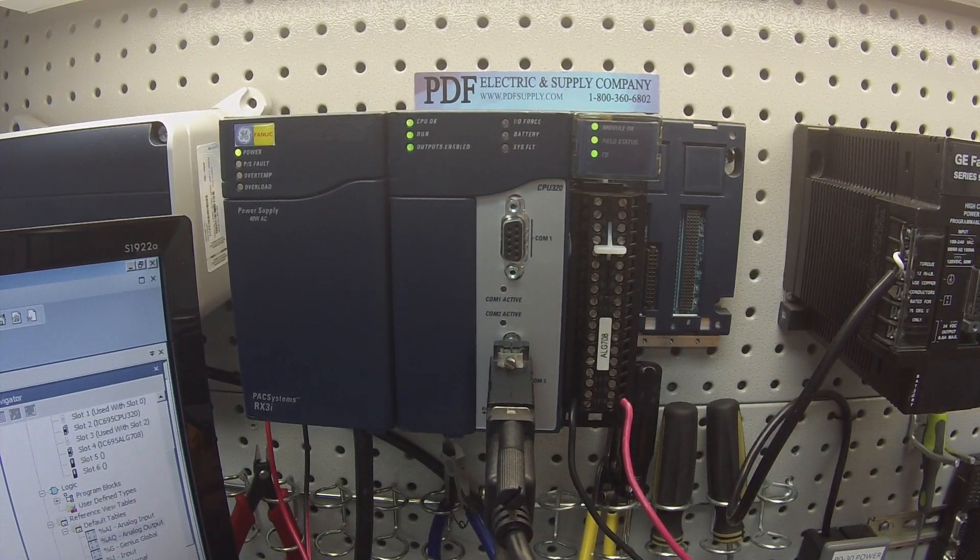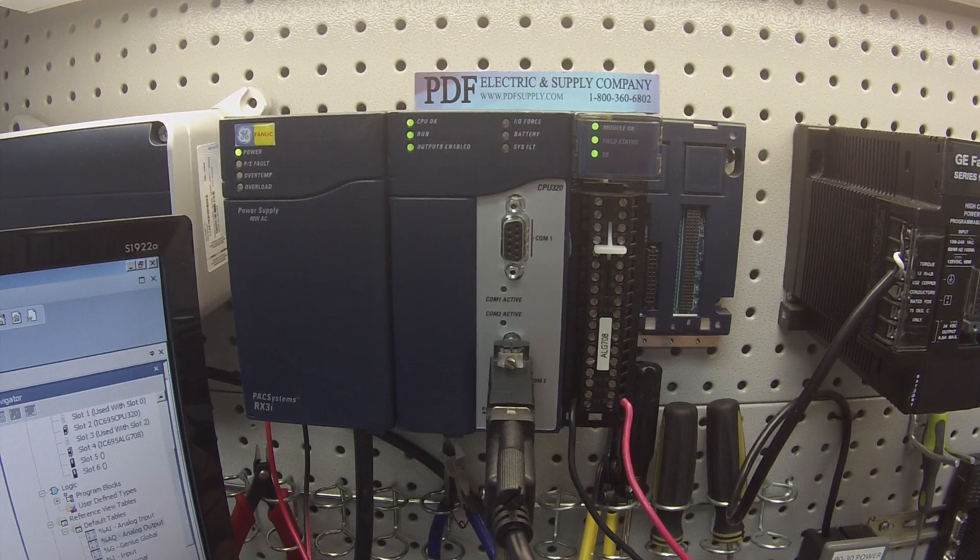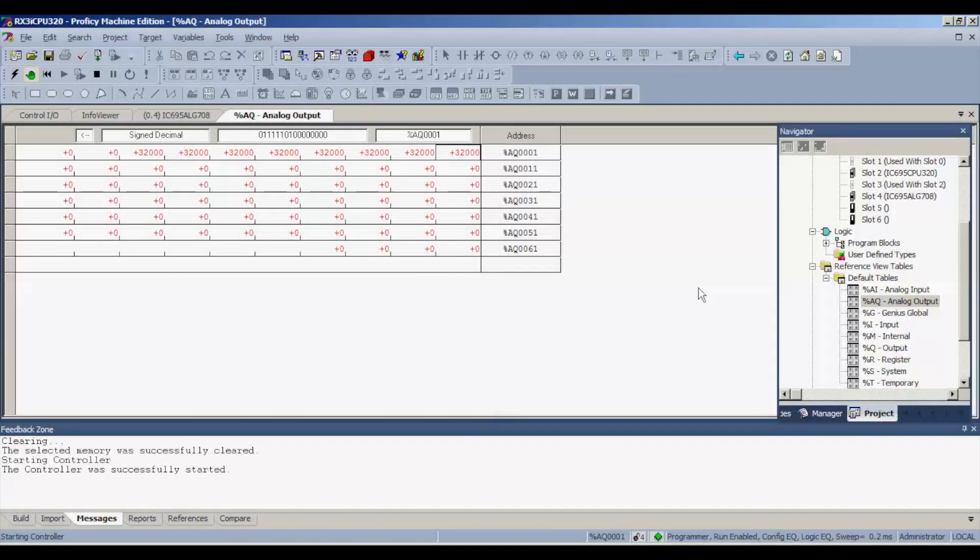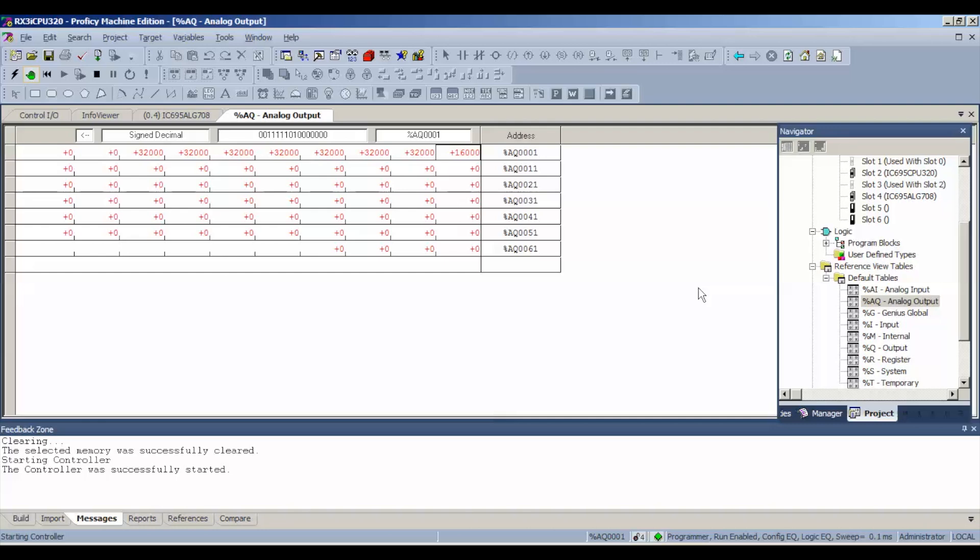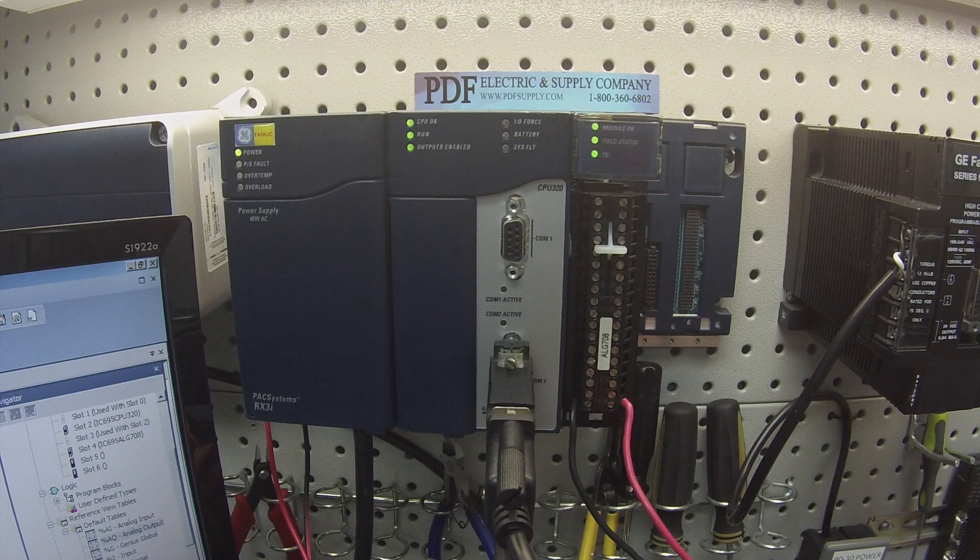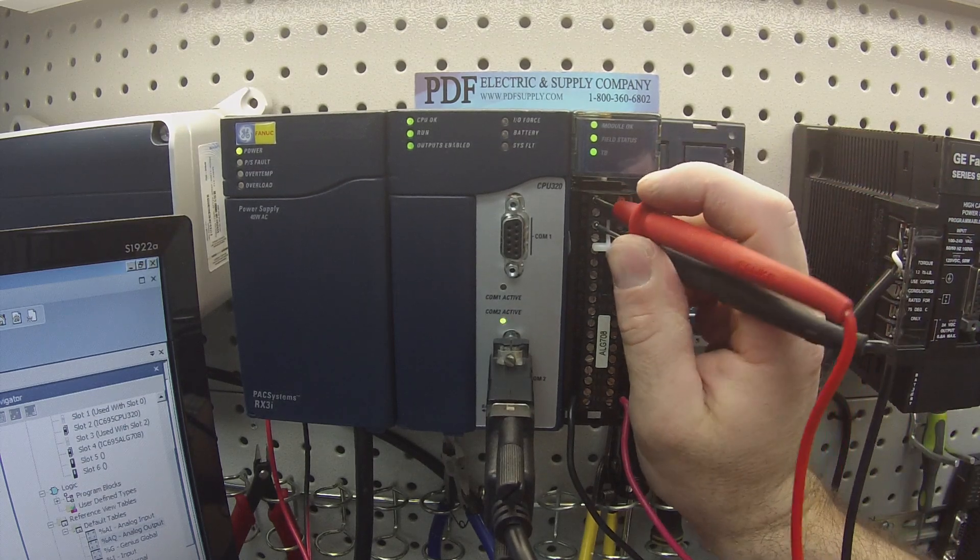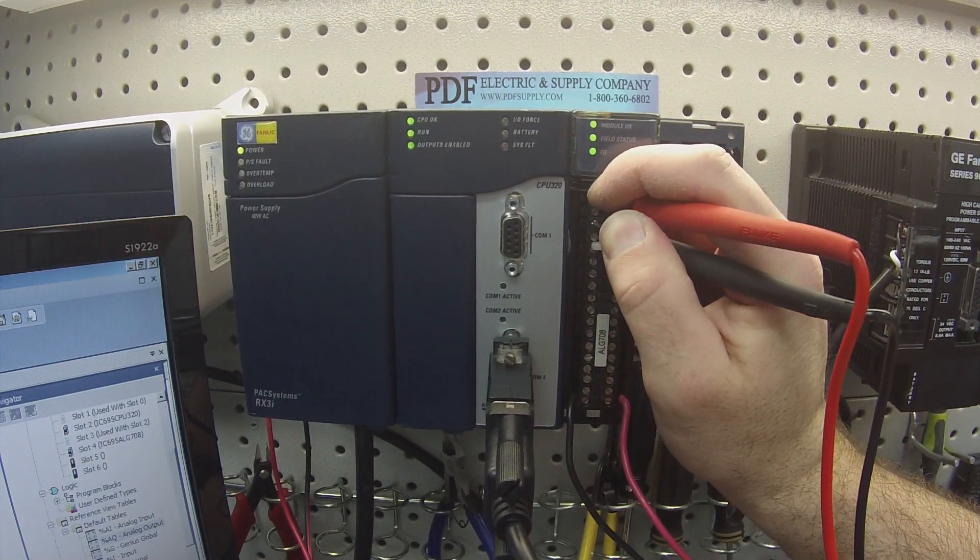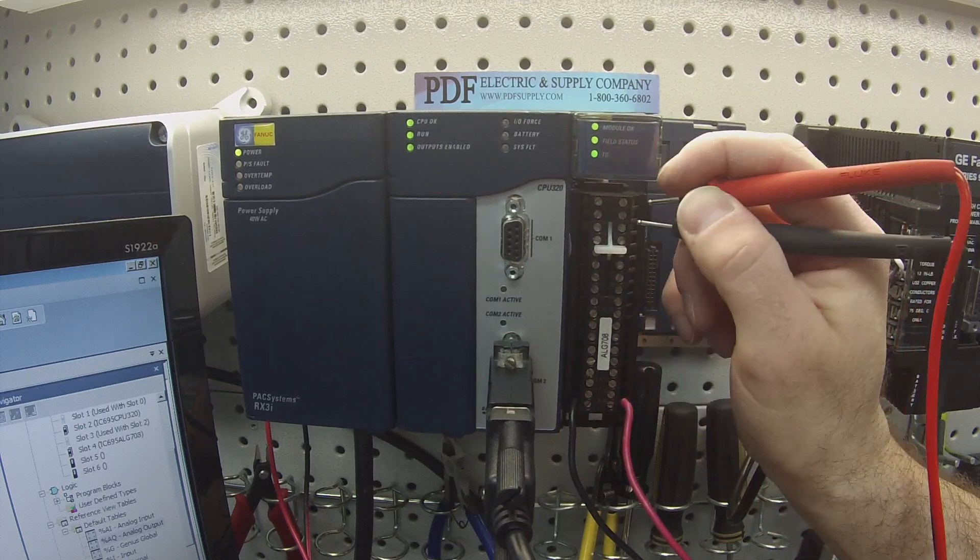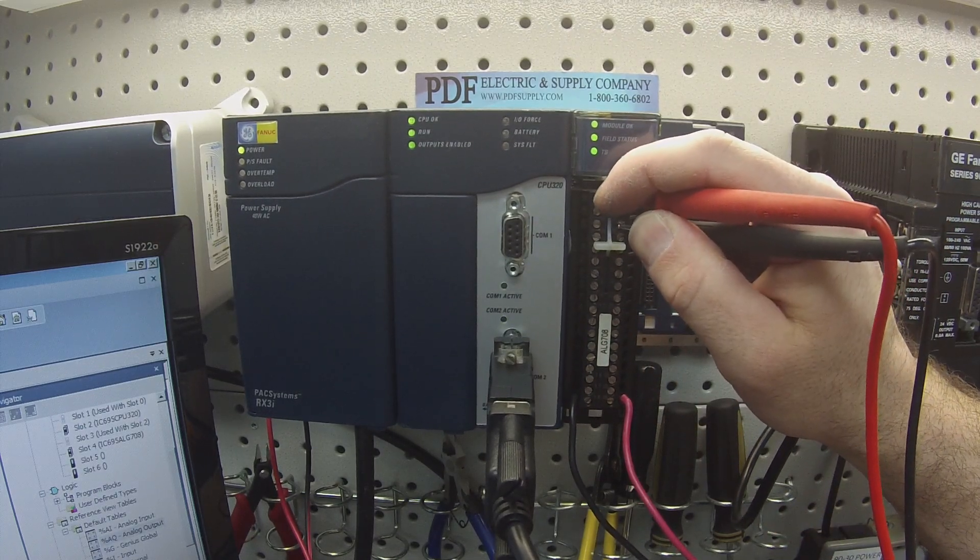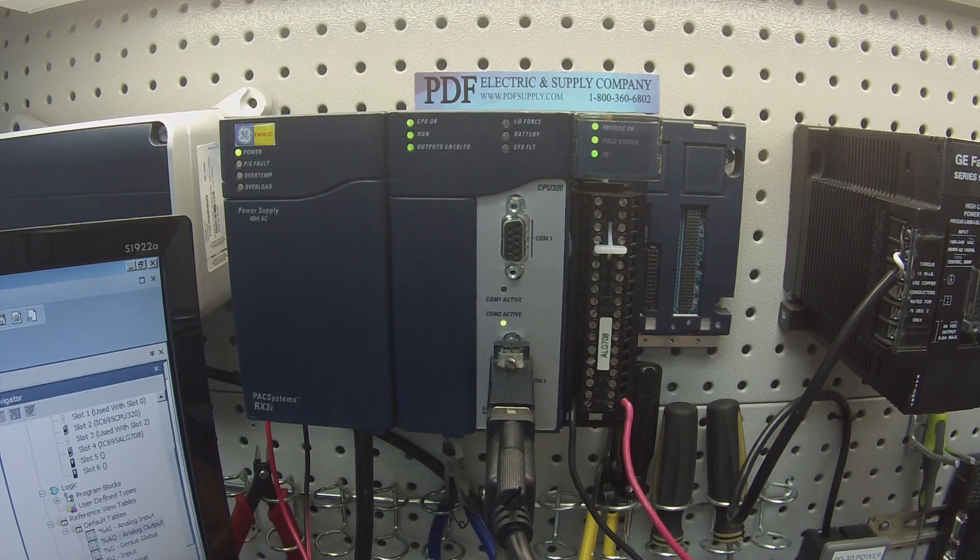However, one thing I'd like you to do if you're going to be testing this to make sure it's in good working order, if you look at the Proficy Machine Edition, I'm going to give that 16,000 as a value, which is half of 32,000, which means it should be half of the voltage. If I was getting 10 volts or 10.5, I want to see five or five and a quarter on this particular voltage. In fact, I do have five and a half volts.